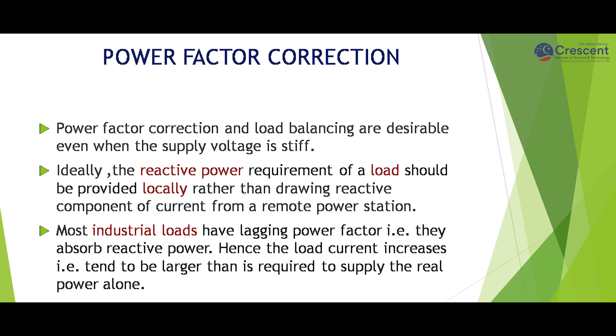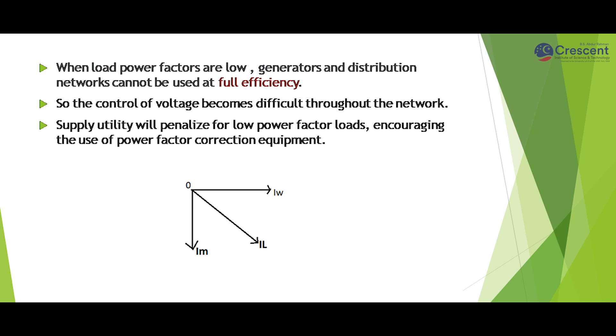Industrial loads tend to draw more current than is required to supply the real power alone. Only real power is ultimately useful in energy conversion. The cost of the excess current — including the larger cables required to carry it and the I²R Joule losses — has to be borne by the consumer.